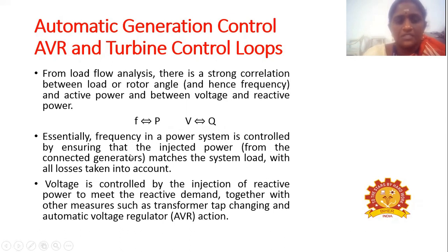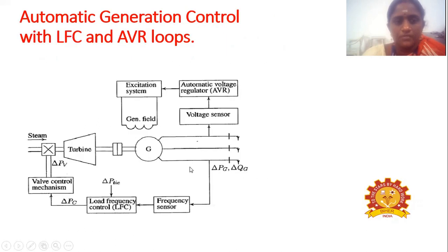The frequency in a power system is controlled by ensuring the injected power matches the system load. If the injected power matches the system load, we can maintain a constant frequency. The voltage is controlled by injecting reactive power to meet the reactive power demand, together with other measures such as transformer tap changing and automatic voltage regulator actions. So if we change the real power, we can maintain the constant frequency, and if we change the reactive power, we can maintain the voltage. Let us see the operation of automatic generation control, and how it maintains constant frequency and voltage.